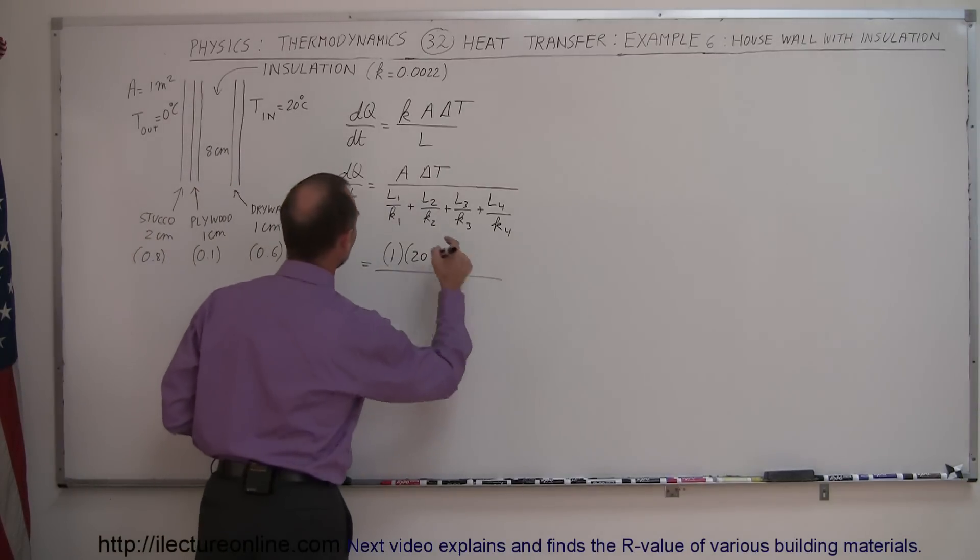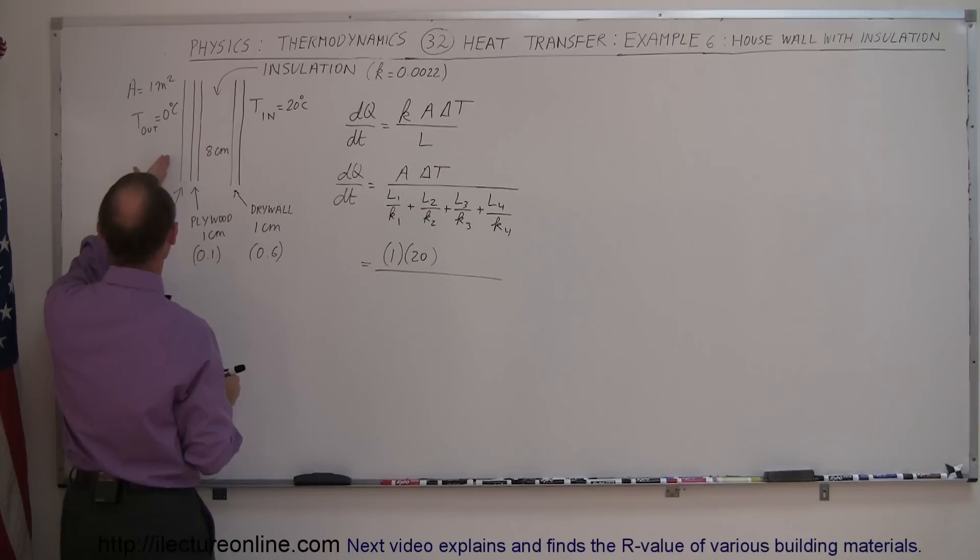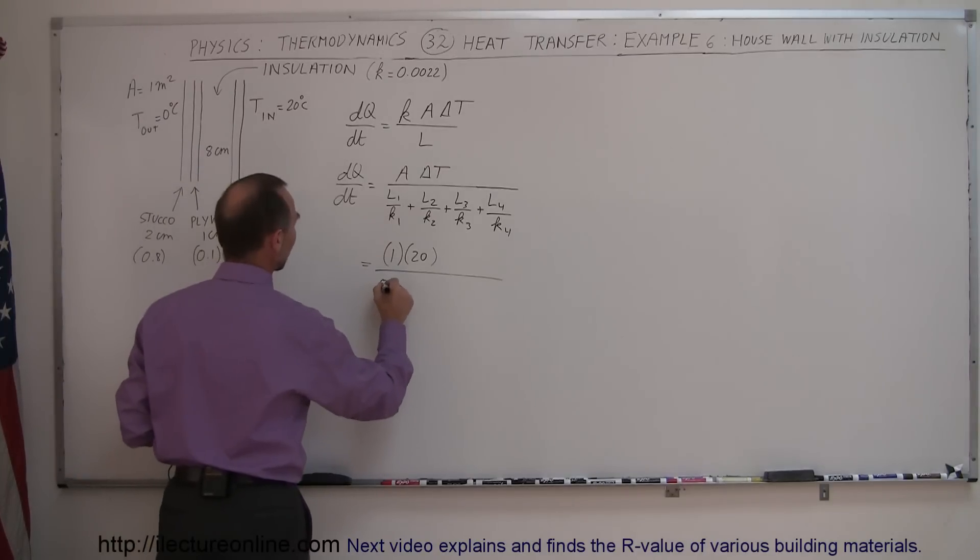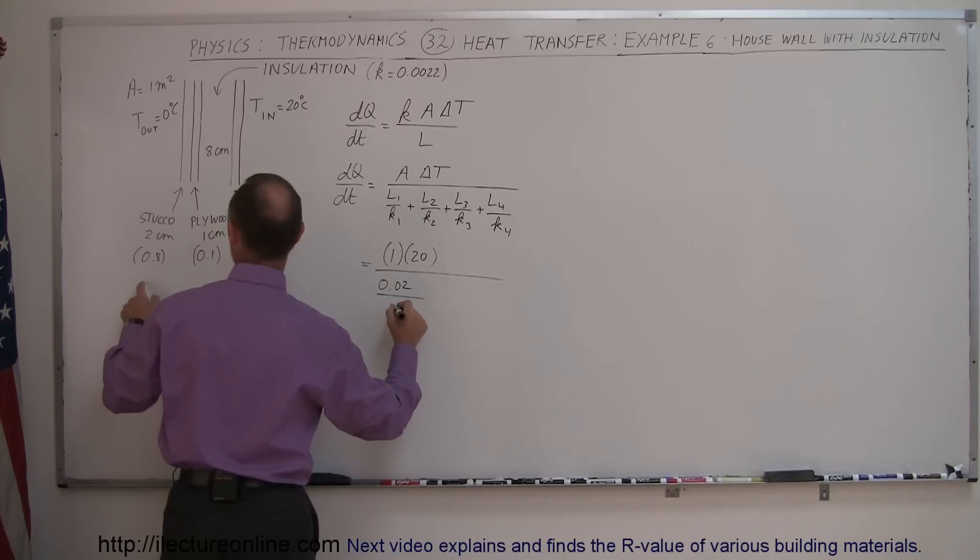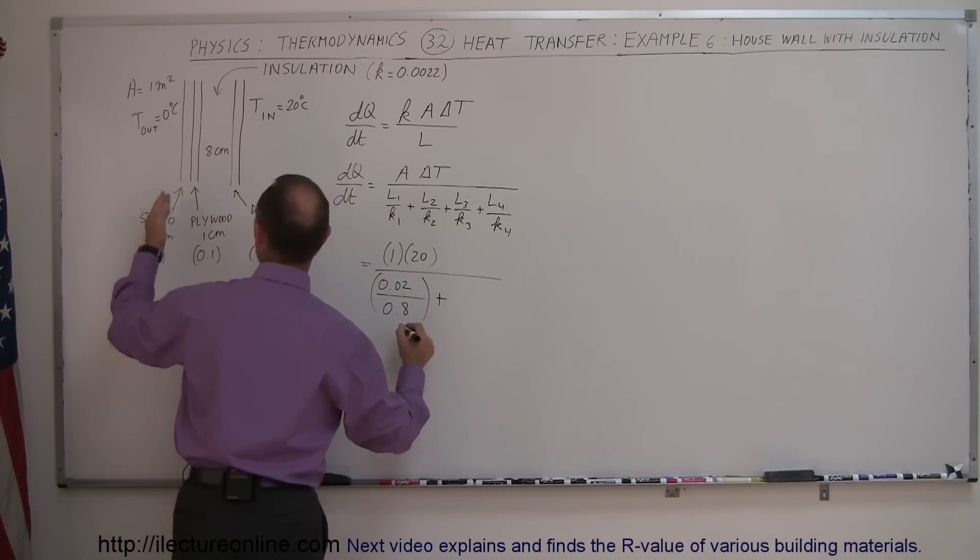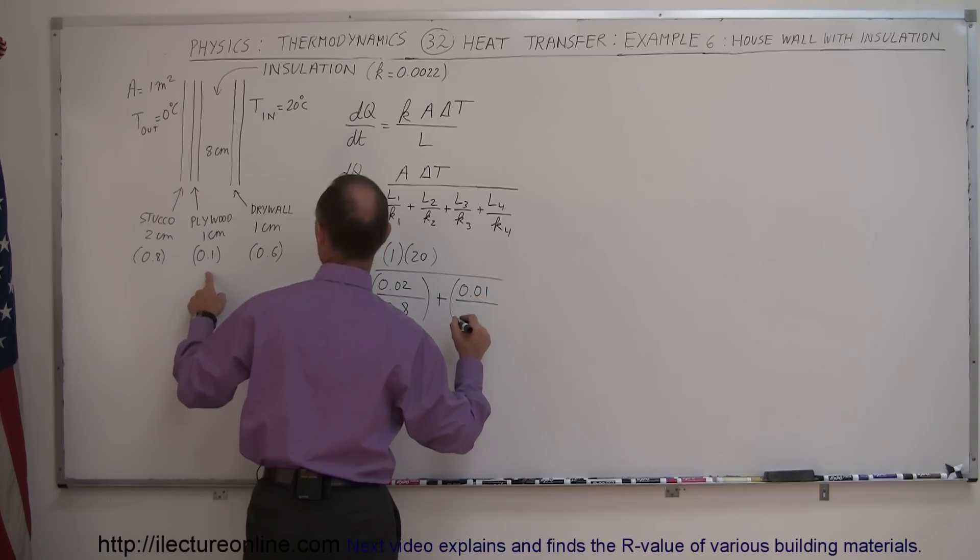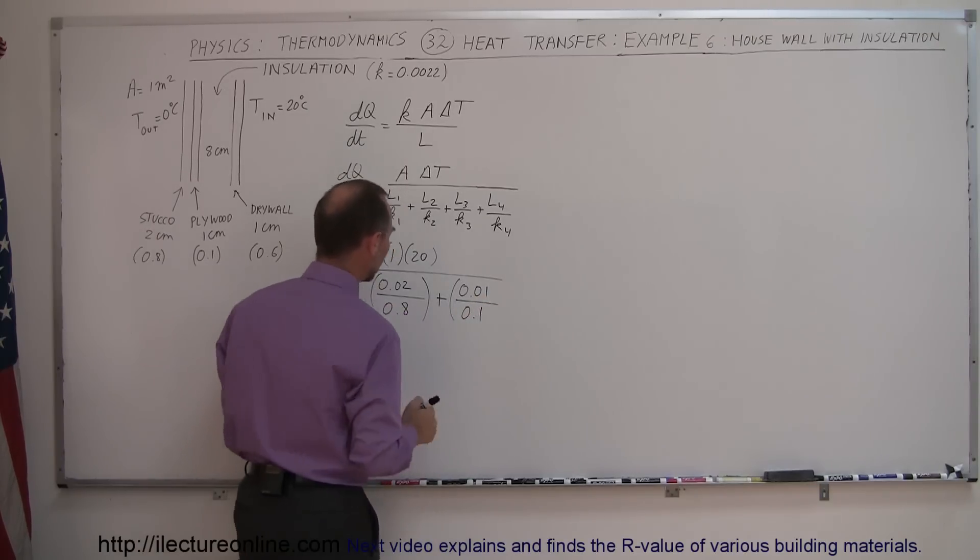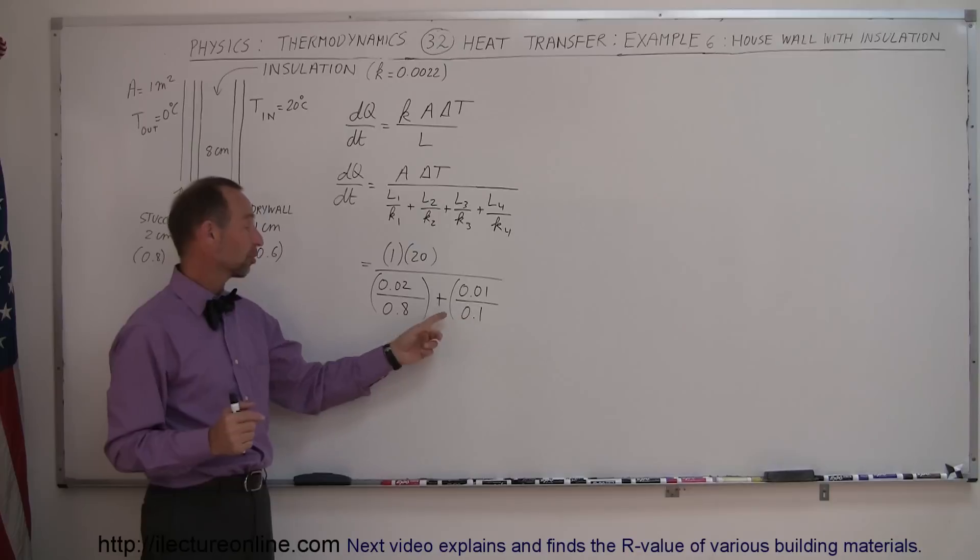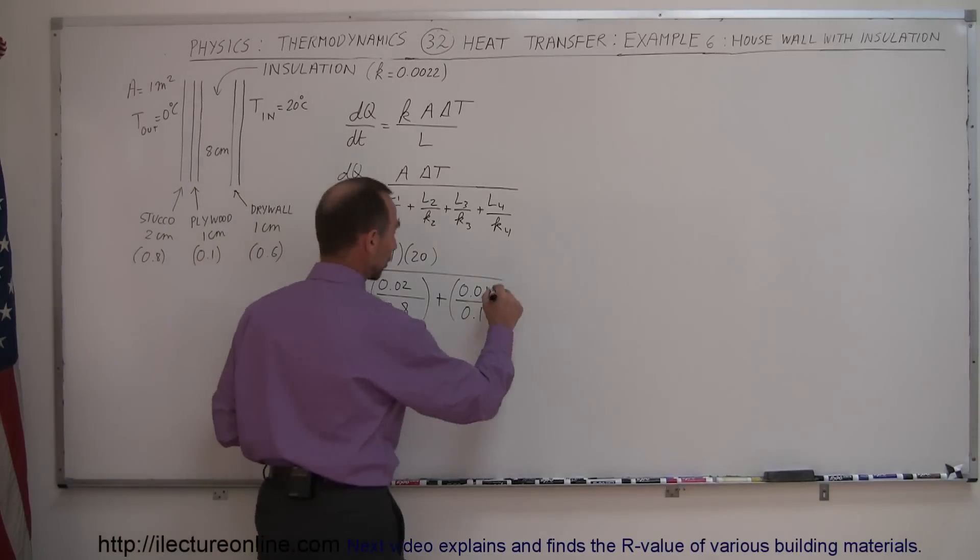And so we divide that by L1 over K1 for the outside stucco. So that would be 0.02 divided by 0.8 for the K value for stucco. Plus then we had the plywood section, 1 centimeter, 0.01 meter divided by the K value of 0.1. Notice how the K value for wood is much smaller than it is for stucco or concrete.